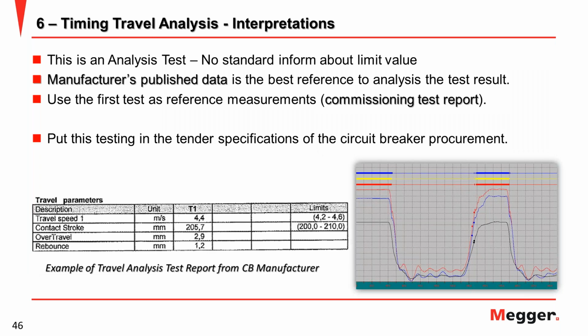This is the interpretation. This is the analysis test. So there is no standard information about the limit value. You can use the manufacturer published data as your reference, or the commissioning test report as your reference. If you don't have all the information, you can do a test at the beginning on a good breaker with the same specification, and then you can use it as your reference.